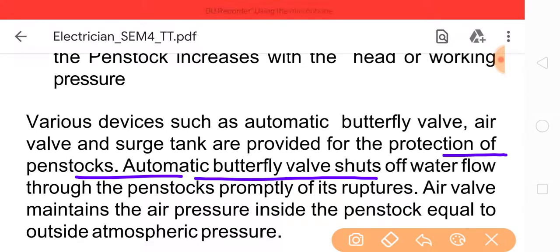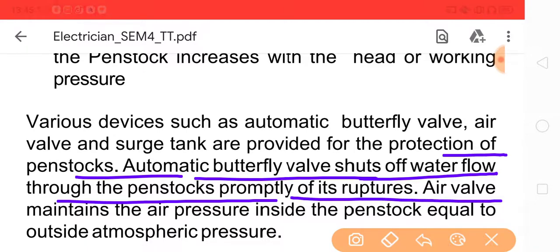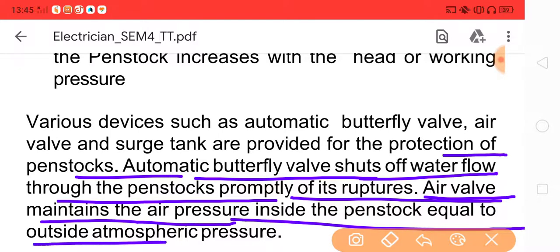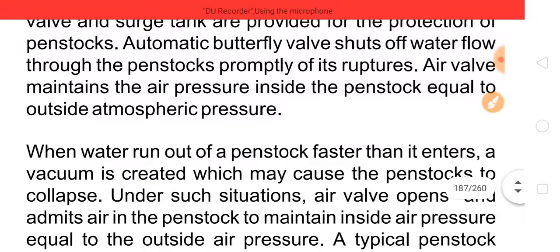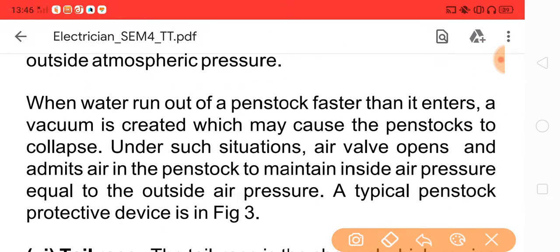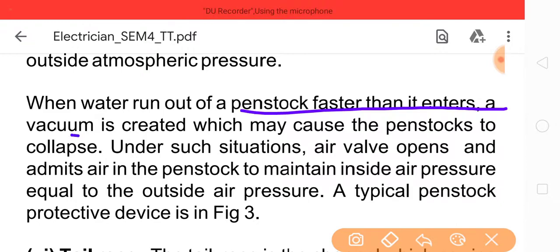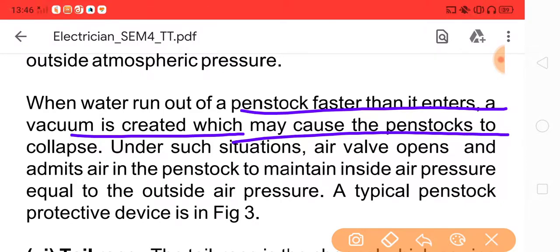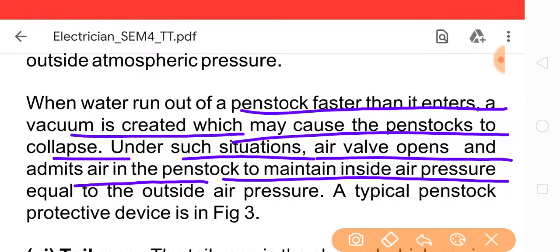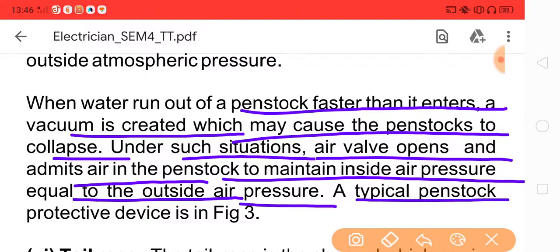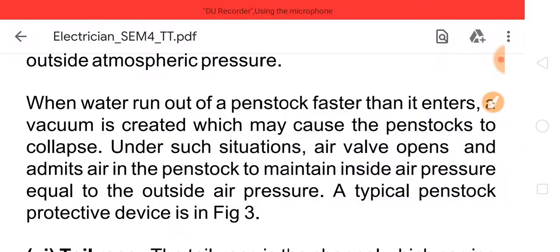Automatic butterfly valve shuts off water flow through the penstock promptly if it ruptures. Air valve maintains the air pressure inside the penstock equal to the outside atmospheric pressure. When water runs out of the penstock faster than it enters, a vacuum is created which may cause the penstock to collapse. Under such situations, the air valve opens and admits air into the penstock to maintain inside air pressure equal to the outside air pressure. A typical penstock protective device is shown in picture 3.